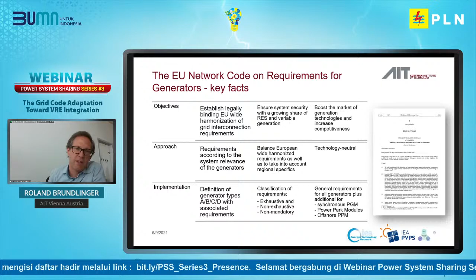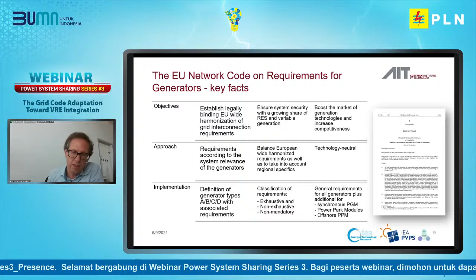The network code is formulated in a technology-neutral way. So there are no specific requirements for solar PV, wind or hydro generation. The requirements are based on the definition of so-called generator types A, B, C, D. These generator types are based on the installed capacity of the generator as well as on the connection voltage level of the network. There are general requirements applicable for all generators, plus additional requirements for synchronous power generating modules, for power park modules, which include all the non-synchronous generators, and specific requirements for offshore generators.